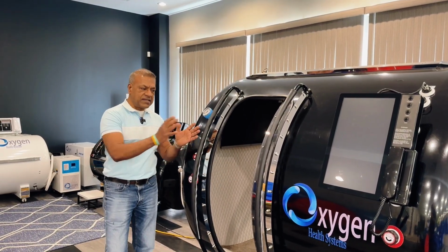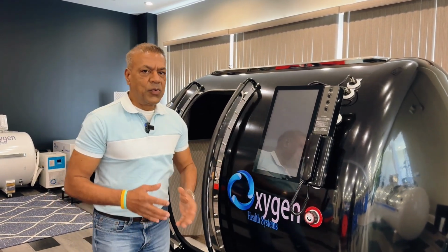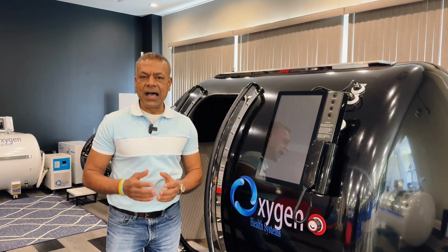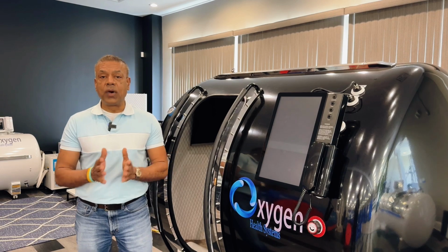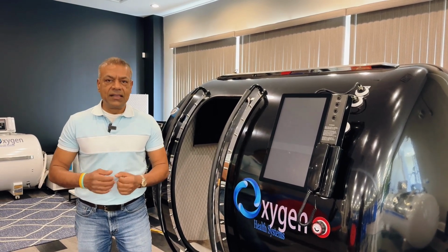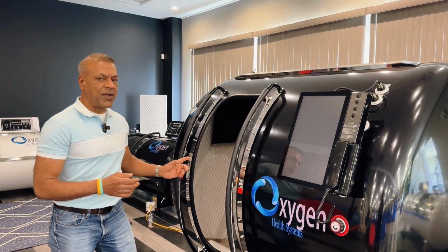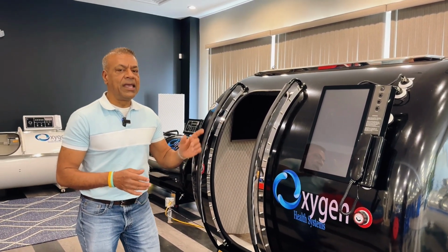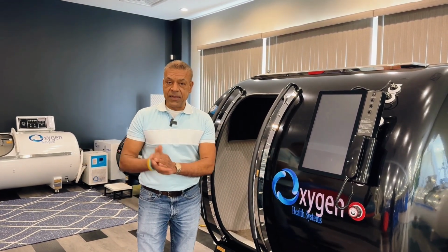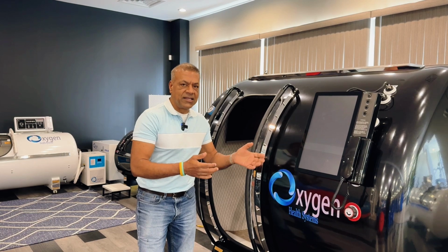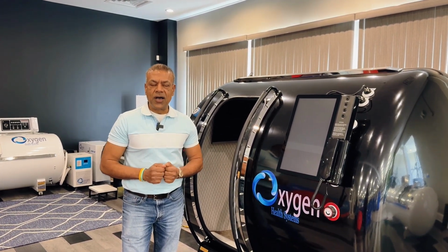While you've stepped out of the chamber, look at the interface. The interface is still dark, which indicates that the power is still out and it hasn't been restored. So hence, it proves that no matter what, if you have a concern about what would happen in the event there is a power outage, we have just demonstrated that there's nothing to be concerned about. Upon engaging these two valves, and also releasing the pressure from inside the chamber to the outside and bringing the equilibrium, the door would open automatically.